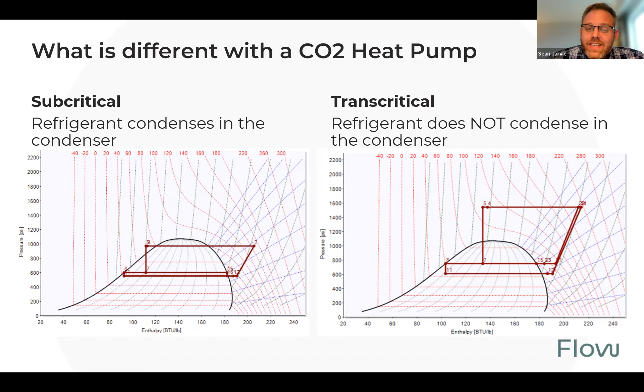So next, I really want to talk about different multiple modes of operation we could put a heat pump into. First one is cooling only. Think of chillers. Think of water cooling systems and air cooling systems. Think of heating only. Think of boiler replacements, condensing boilers, heating heat pumps, domestic hot water heating, etc. But what's really unique with the heat pumps we've designed, that are very unique in the marketplace right now, is they utilize a truly simultaneous heating and cooling loop, meaning we can extract heating and cooling at the exact same time in the same unit, in the same circuit. There is no reversing valve like most subcritical HFC, HFO type synthetic refrigerants have. And I'll get into that in the follow-up slides. Operational range right now is huge. We're going from 0 degrees to 120 degrees right out of the gate.